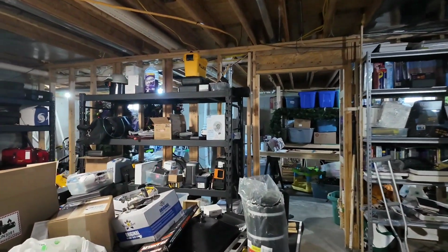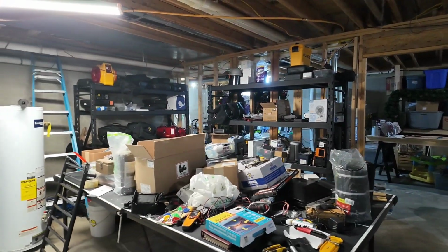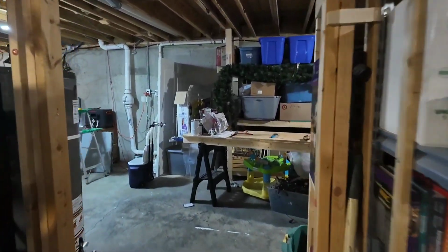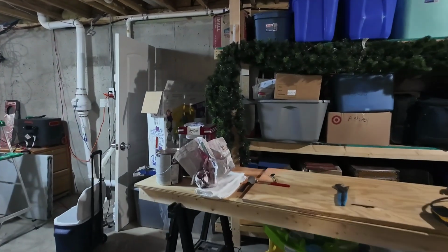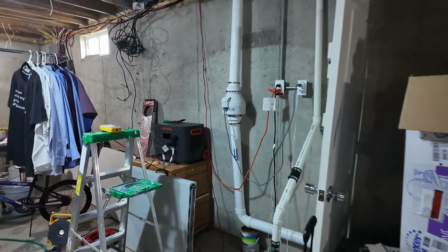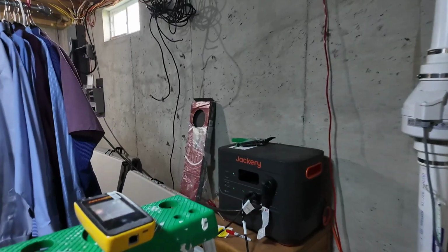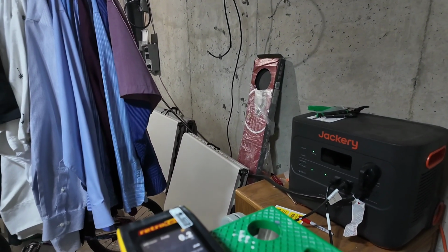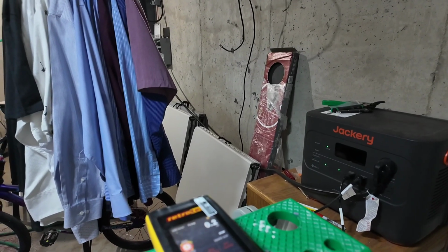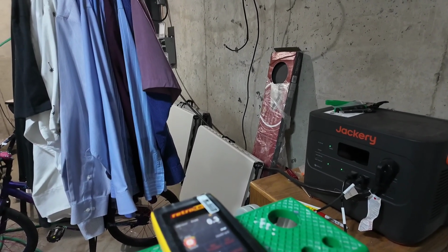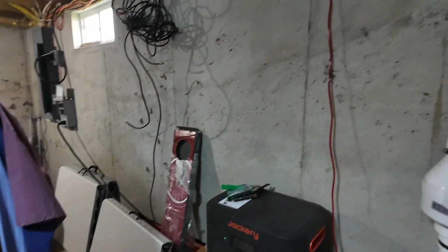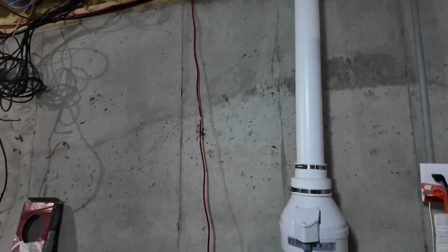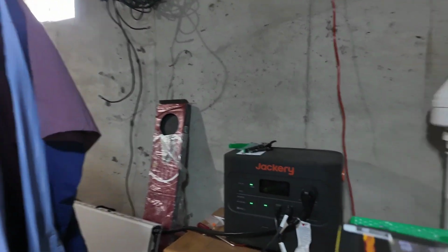The CAS door shall be closed. Using a calibrated manometer or similar pressure measuring device intended for this purpose, measure and record the baseline pressure in the CAS with reference to the outdoors. We had to run a tube to the outdoors. We did this earlier. It's connected to our micromanometer.